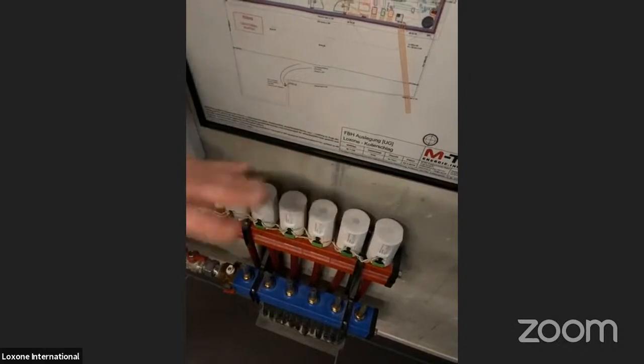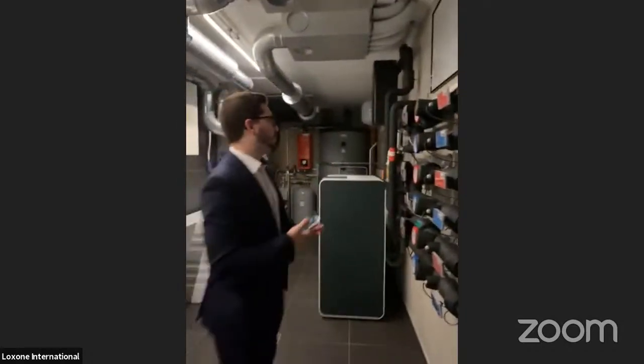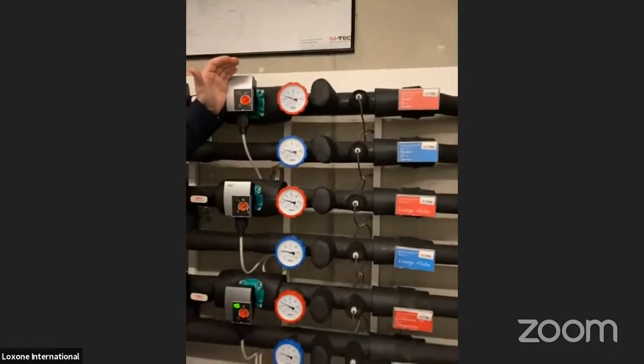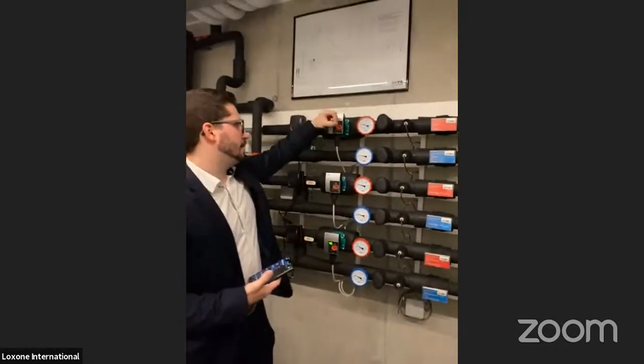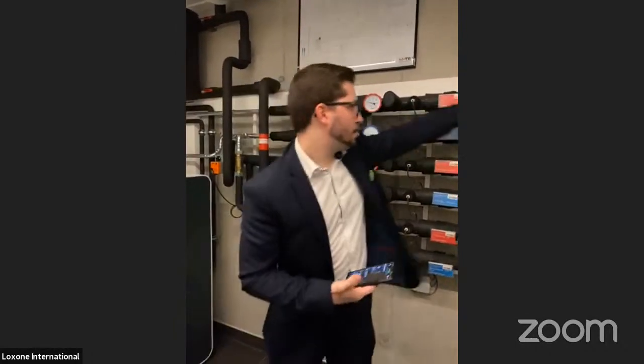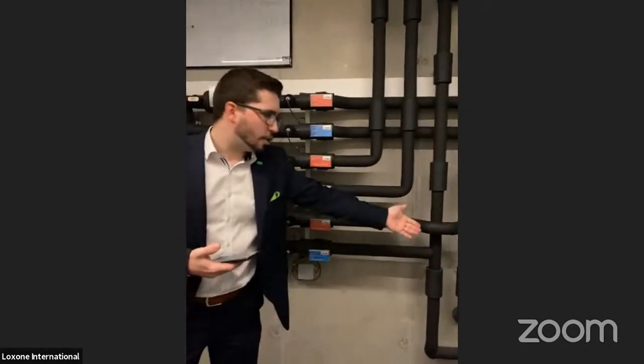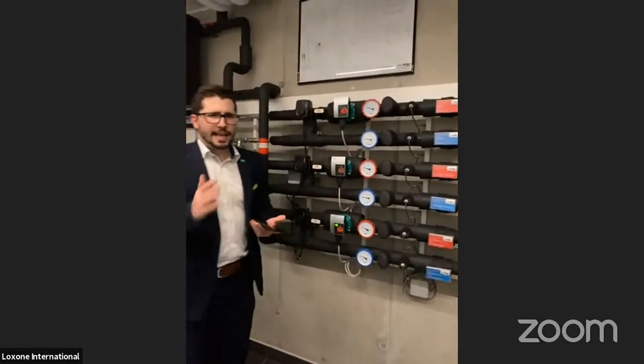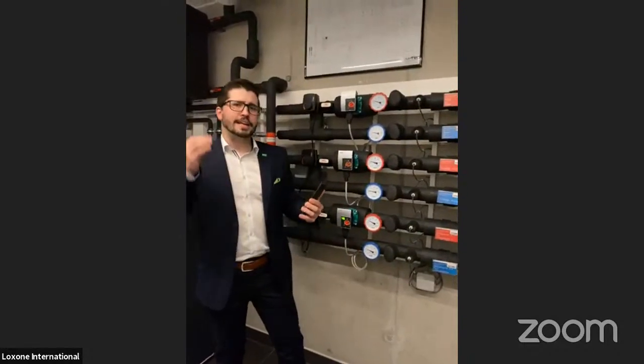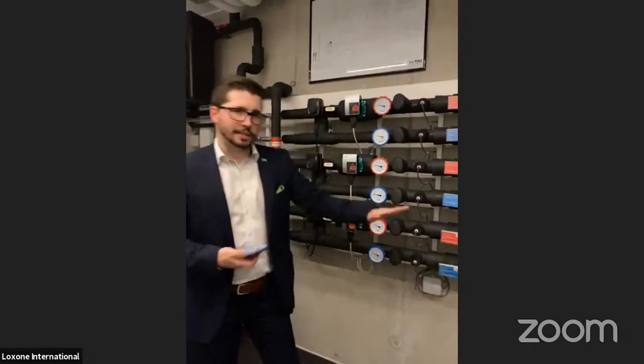On a room basis like this, you can reach, let's say, 80% of efficiency. But if you want to go all in and really save and get the most out of it, then you can integrate the system in a very deep way, like controlling the mixing valve. It's like in the shower: you change the temperature with this thing here, hotter or colder. It does the same to reach a certain flow temperature, which goes to each room. Depending on the temperature here and on how far you open the individual rooms, you get a certain temperature. If the system knows that just the bathroom, a small room, needs heat and all the others are fine, then please don't go with the maximum flow temperature. Go lower, save money, and you still get the same result.